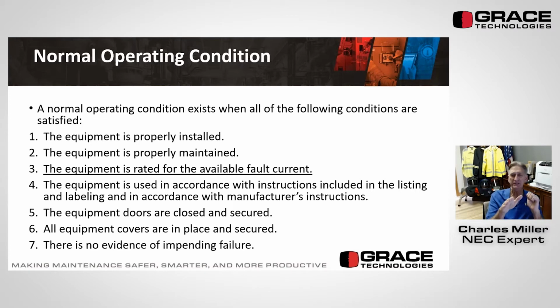Now, the equipment door, sometimes there was confusion on this. You think, wait a minute, if the door to the breakers is closed, I can't turn the breaker on or off. That's not the door it's talking about. That door is just making a good cover to the front, maybe even able to lock the front cover off. It's talking more like an industrial control panel door, or even a door to a breaker box that would be on hinges and could swing open. All equipment covers had to be in place and secured, and there has to be no evidence of impending failure.